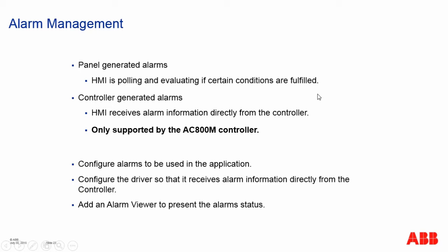But in the case of the AC800M controller and the MMS driver, we can also use controller generated alarms. It means that the alarms are handled in the PLC directly, and the HMI is just receiving the alarm information directly from the controller, which will make it much quicker to develop the application and easier to maintain.